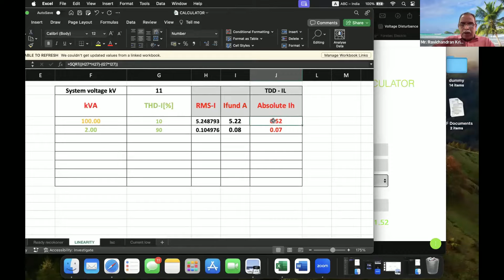From that, we find the resonance frequency, and if there is harmonic distortion, we find the absolute harmonic current value. Then we identify which order is predominant. These are the key points for designing the filters.